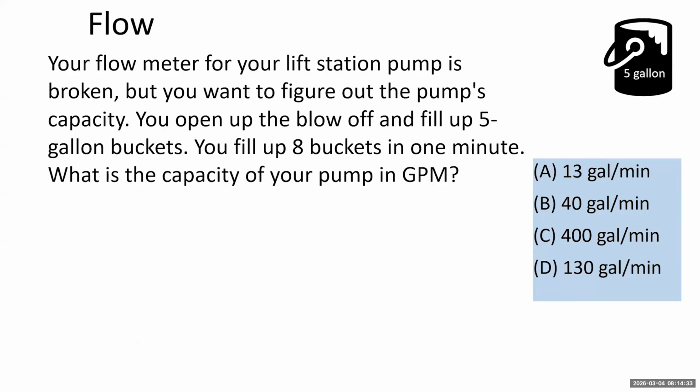So if we're looking at flow or volume, you are going to be measuring things slightly different. So your flow meter for your lift station pump's broken, but you want to figure out the pump's capacity. So you open up a valve and fill up a 5-gallon bucket, and you fill up 8 buckets in 1 minute. So what's the capacity of your pump in gallons per minute? So this is just a simple way to think about flow, right? How much water is moving through that pump or that pipe?